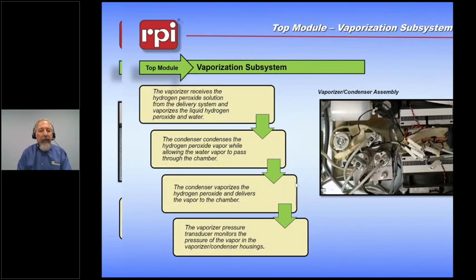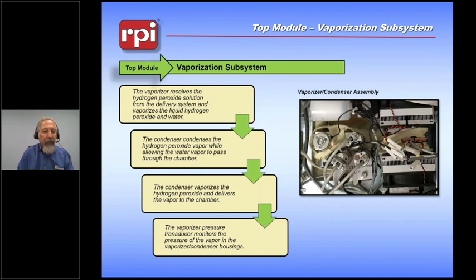Okay, so what happens in the vaporizing system? Well, we take the hydrogen peroxide that we got out of the cartridge, and it comes to us as a mixture of water and hydrogen peroxide at 59%. We need to concentrate that down.